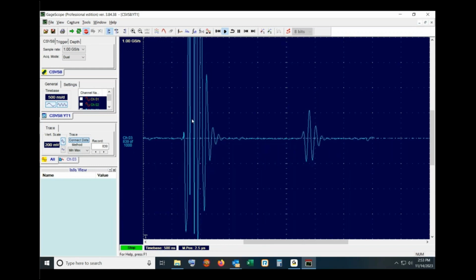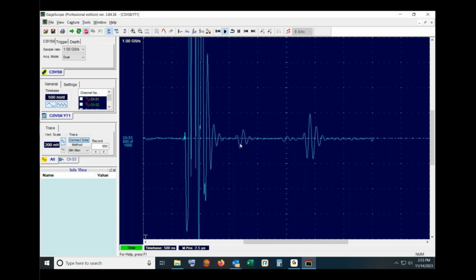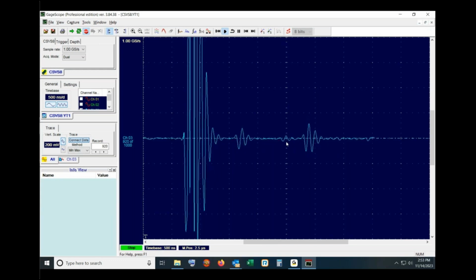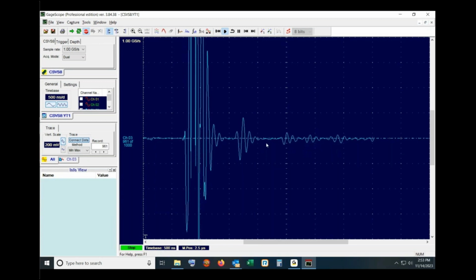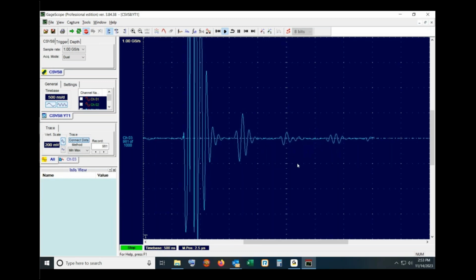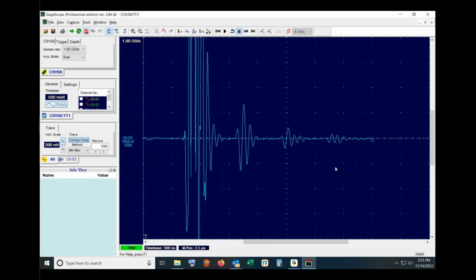So then we'll see the final echo, the shallow hole. We even get, as you can see, 2 reverberations there. We've got a second hole, a second echo - that's the sound bouncing off the hole, bouncing back off the front wall, and then off the hole again a second time. And as you see, we always get the back wall echo a bit because the area of the hole is smaller than the area of the transducer.